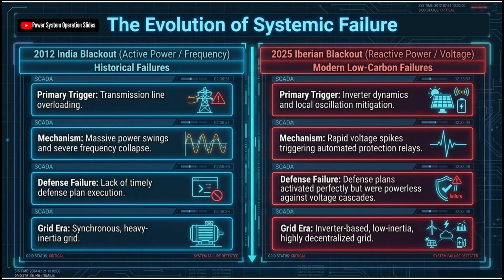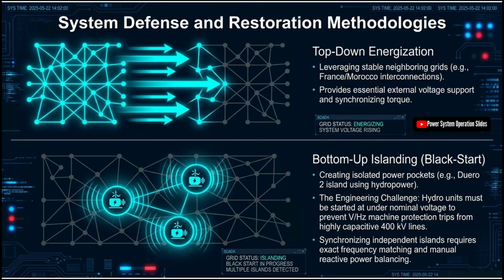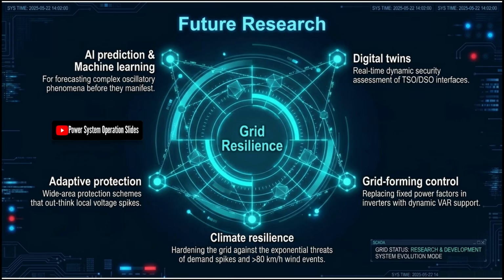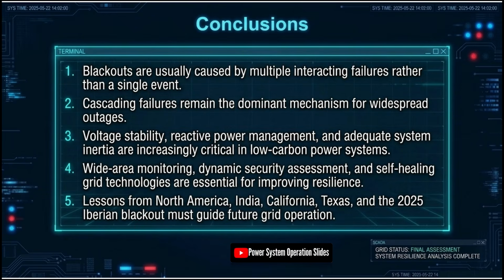It requires maintaining sufficient thermal capacity, voltage stability margin, reactive reserves, frequency reserves, inertia, protection security, situational awareness, and operational flexibility while considering credible contingencies and extreme events. The principal lesson from international blackout experience is that system resilience must be continuously assessed before, during, and after disturbances. A reliable future grid will depend on combining strong physical infrastructure with advanced monitoring, dynamic security assessment, intelligent protection, coordinated operator actions, and new control technologies capable of managing an increasingly complex and highly inverter-based power system.